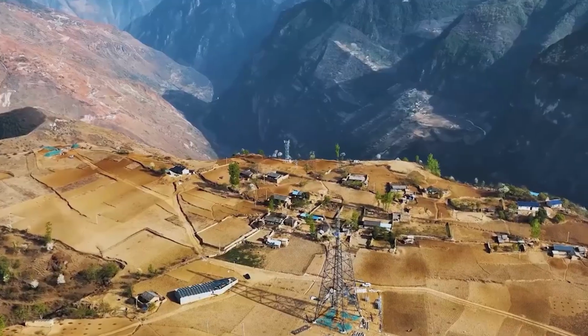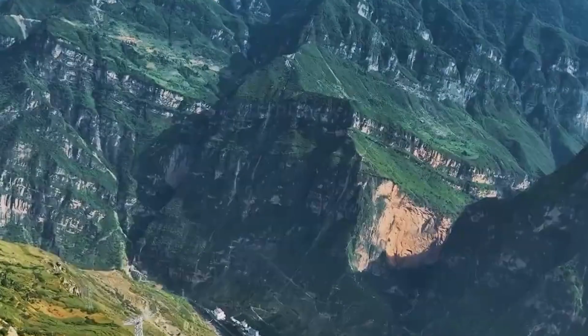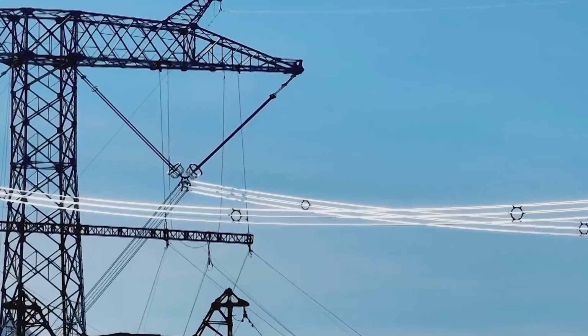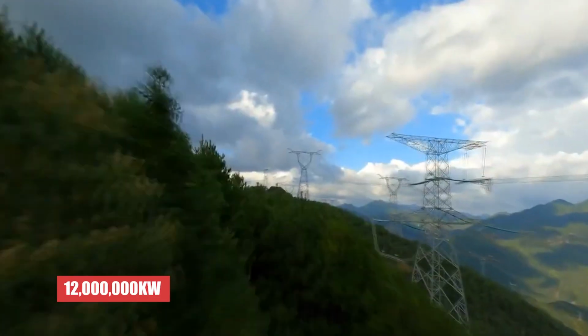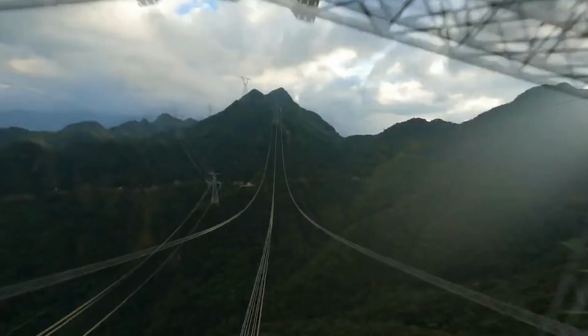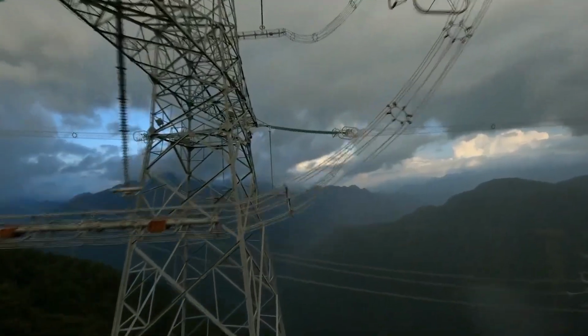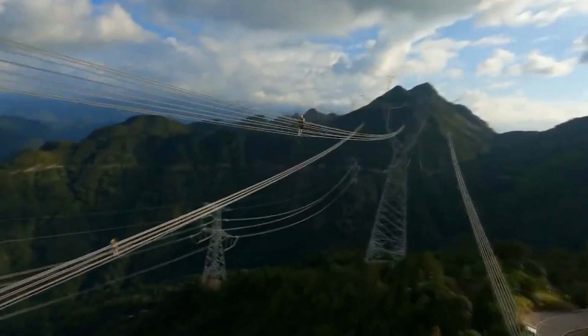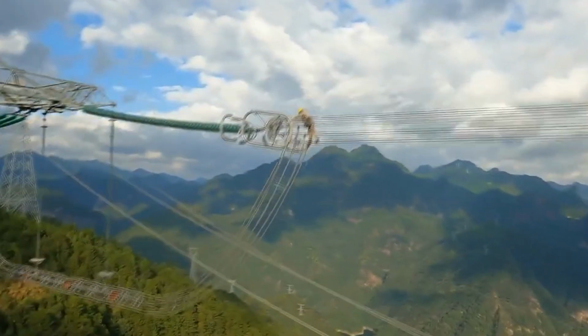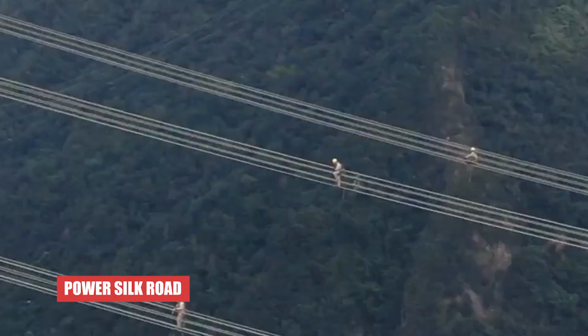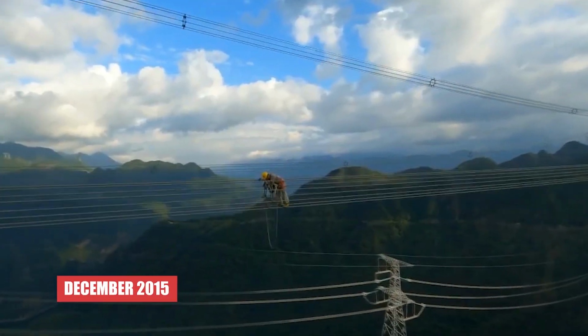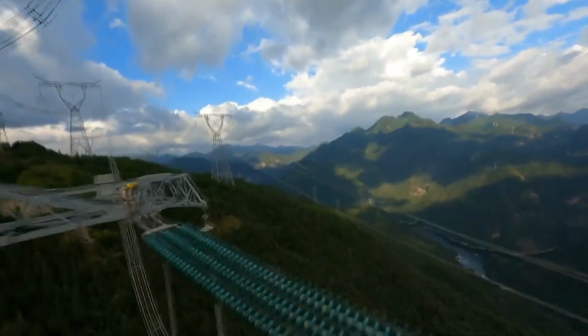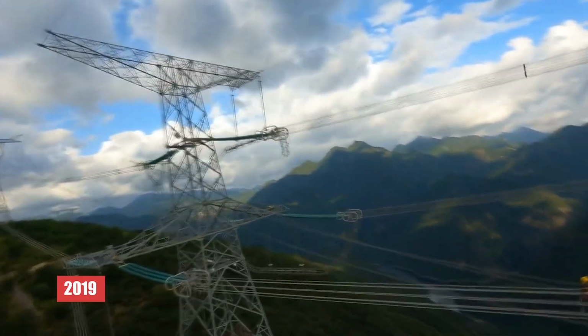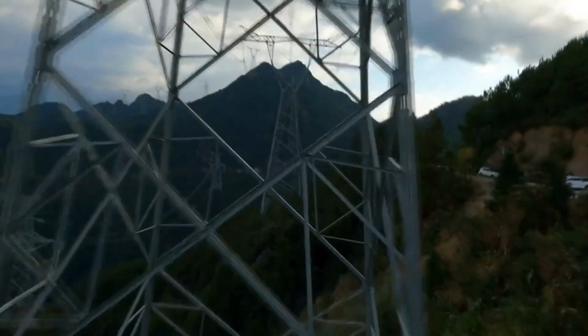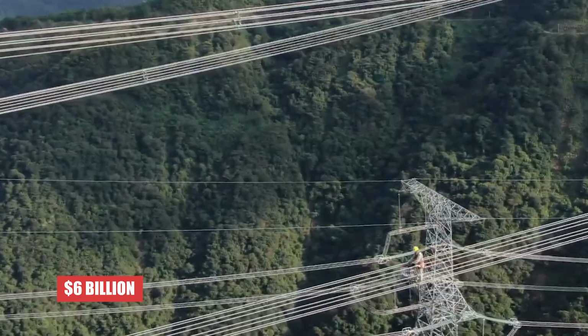It operates at plus or minus 1,100 kilovolts of direct current, the highest voltage any commercial power line has ever run at anywhere in the world. Its capacity is 12 million kilowatts, enough to meet the annual electricity needs of roughly 50 million homes from a single transmission corridor. State Grid Corporation of China, the state-owned utility that built it, nicknamed the project the Power Silk Road. It was approved in December 2015, broke ground the following month, and was fully operational by 2019, at a cost of roughly 40.7 billion yuan, close to $6 billion.